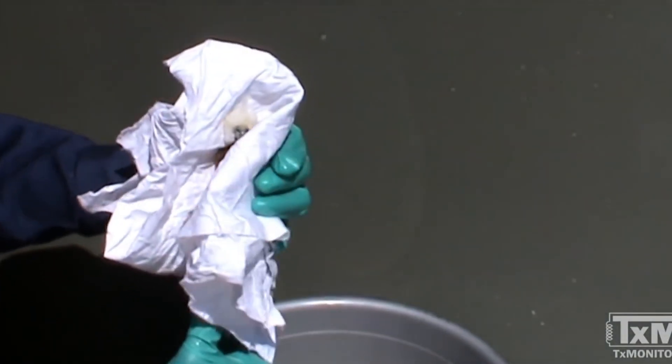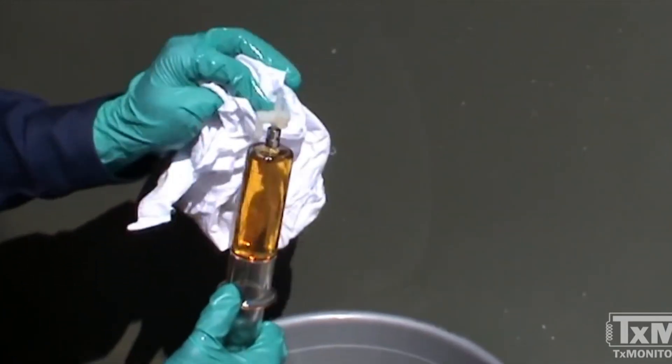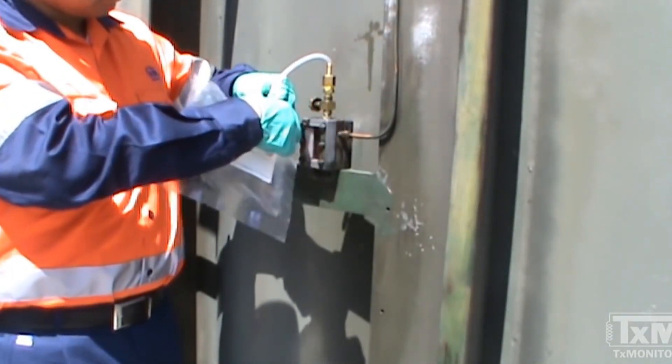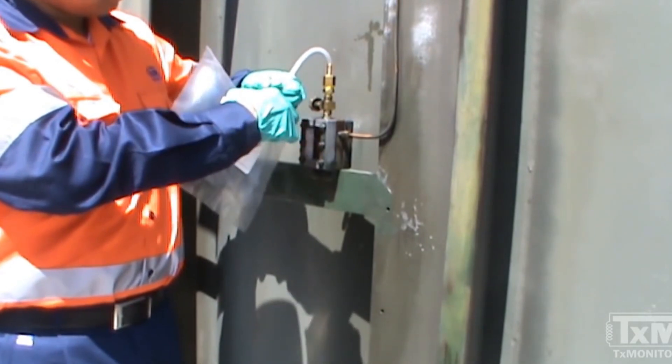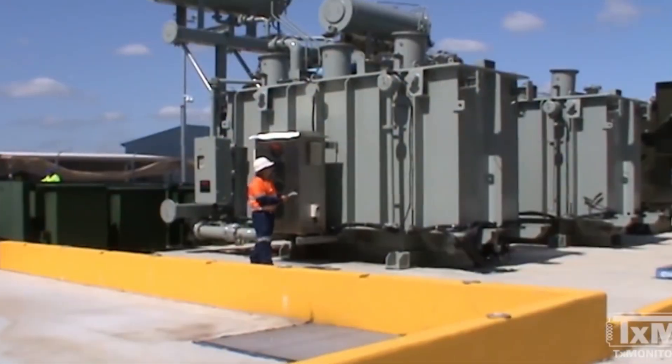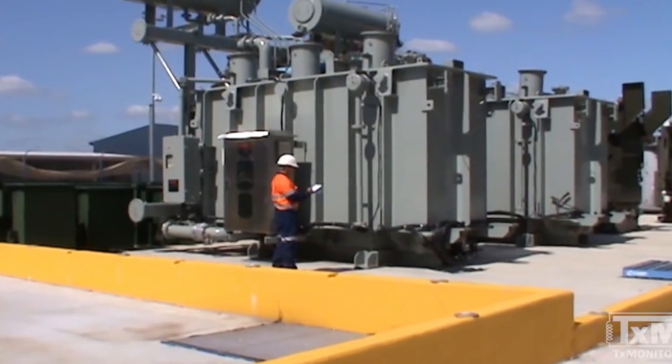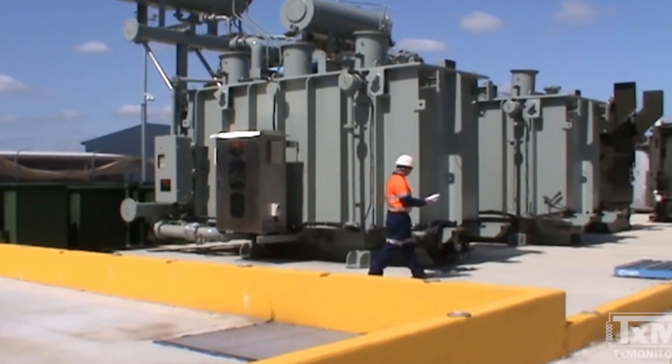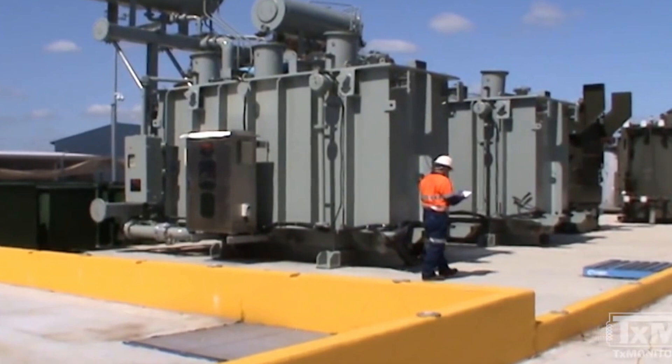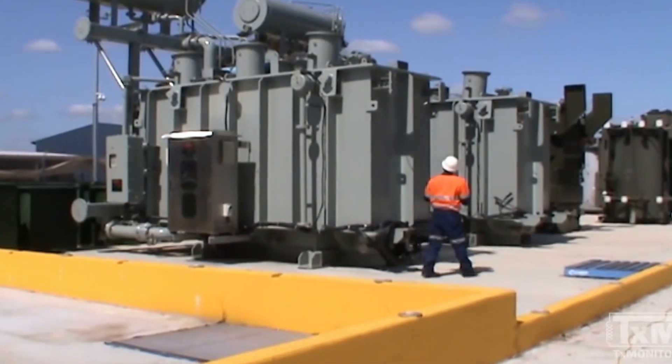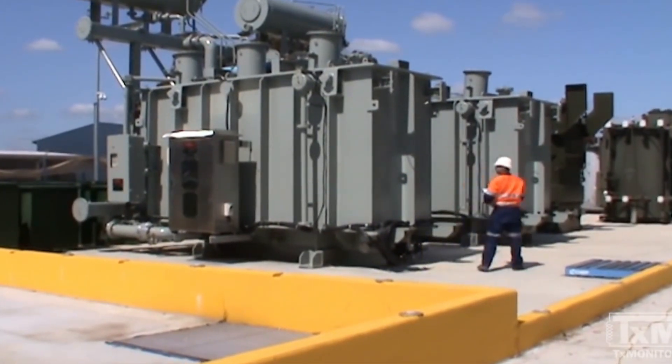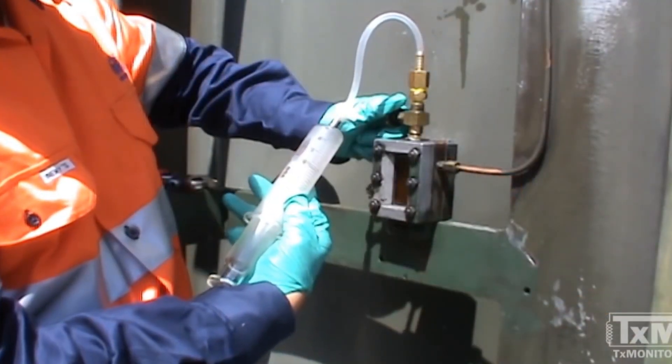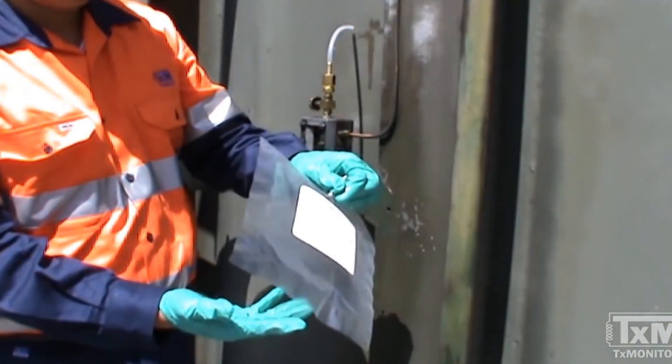A Buchholz can be either sampled for oil or gas. In this video, the techniques for sampling both are demonstrated. If the Buchholz contains accumulating gas that needs to be sampled, the gas can be retrieved using a variety of sampling containers. In this video, the sampling procedures for glass syringes and gas sampling bags are shown.